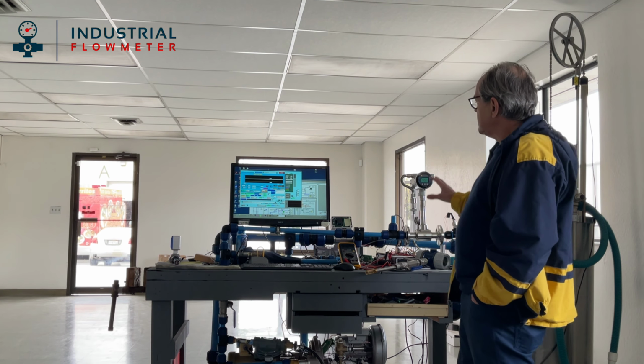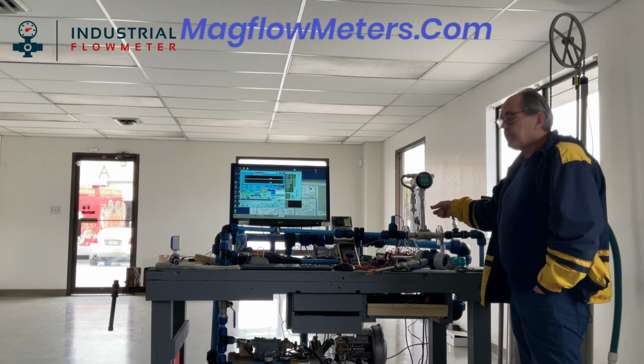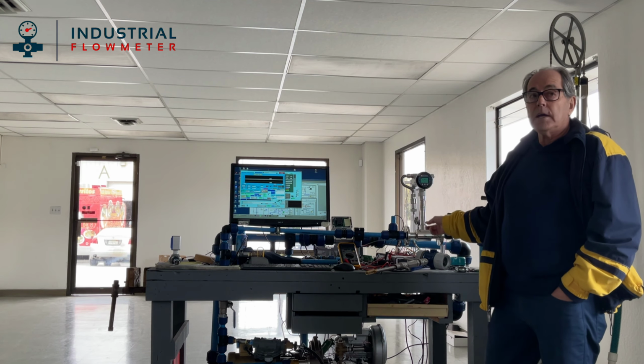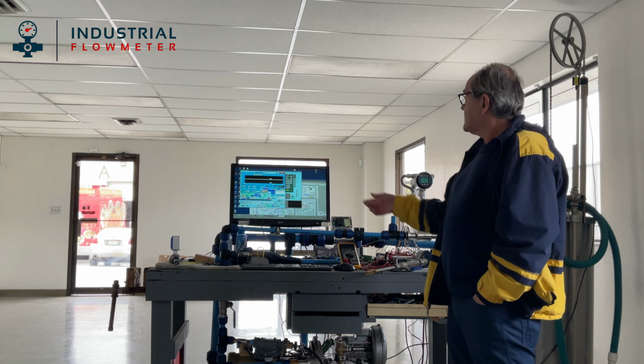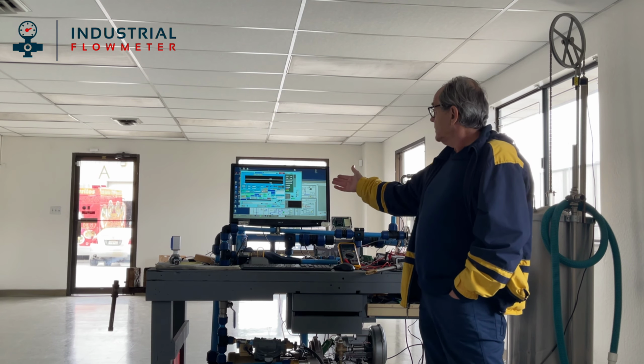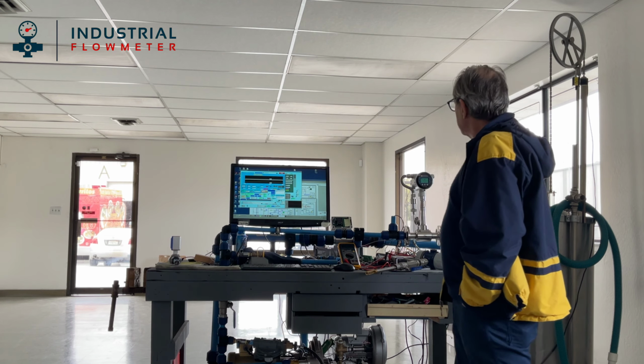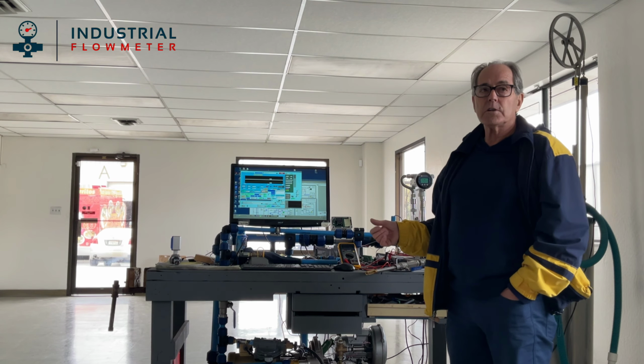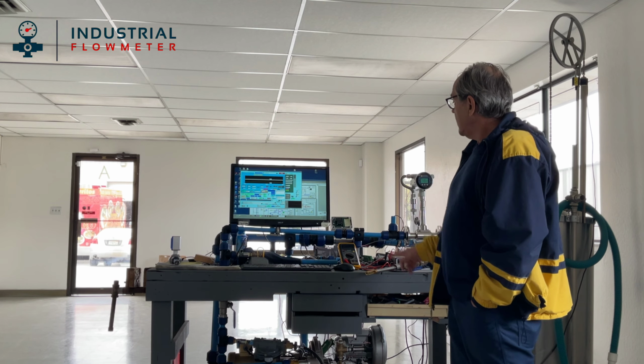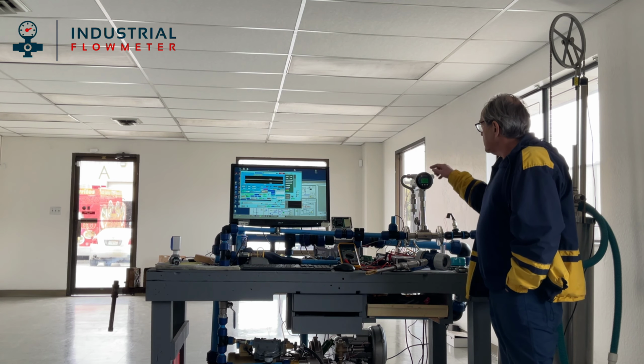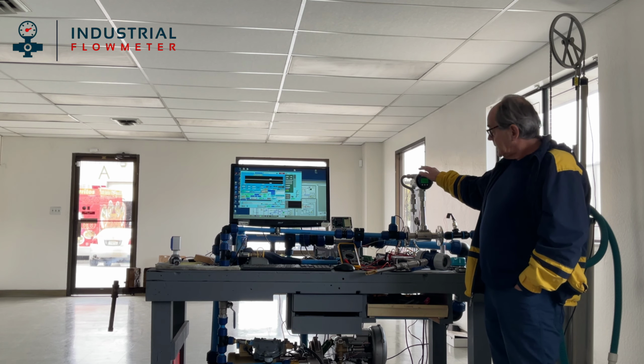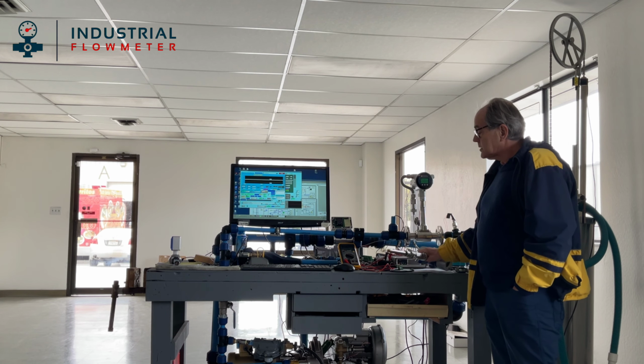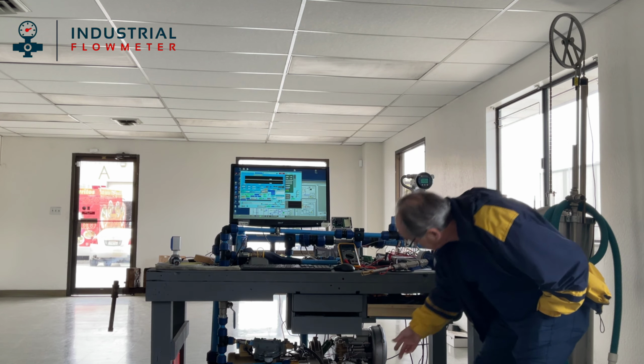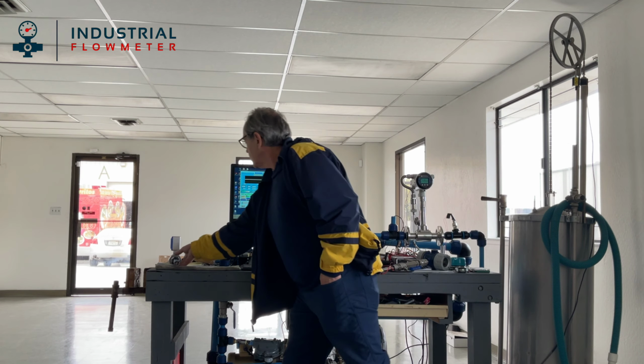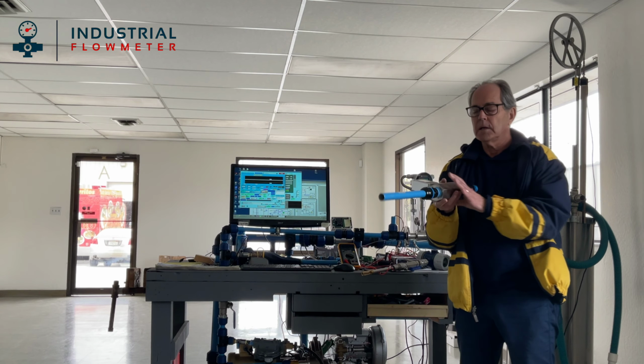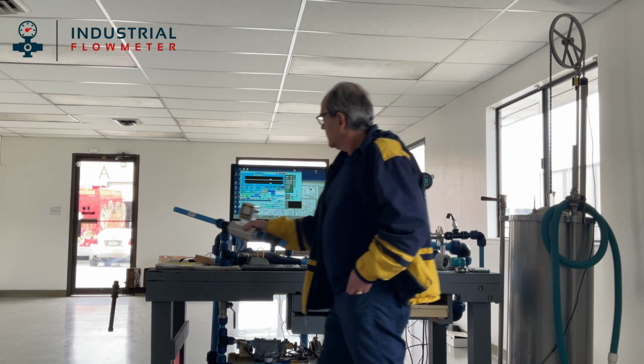And I would say this is a method of characterizing a flow measuring instrument. So it characterizes and it speaks in its native tongue, which we've made standard cubic feet per minute, that can be converted to any unit at any reference temperature and any reference pressure, and then take that characterization and program it inside of any device, this device or this device or the other one.